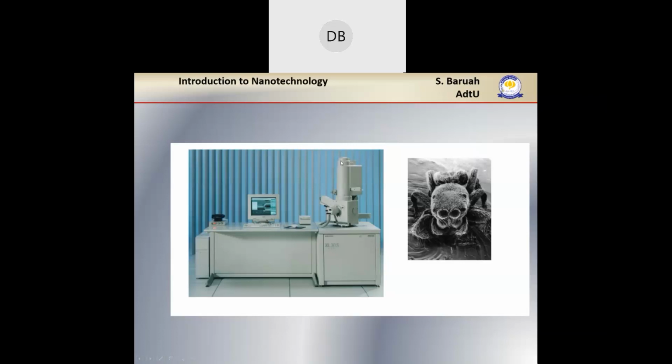So in order to have just the electrons moving, and that too at a very high velocity without any obstruction, we need to evacuate this column. We call it a column. Okay, this column we have to evacuate. That means we have to use a vacuum pump to force out the air from there and create a vacuum inside. Now, when I say vacuum, that means we bring the pressure to an extremely low value. Say, in torr, maybe 10 to the power minus 5 torr. And compared to the atmospheric pressure, that is extremely low pressure.